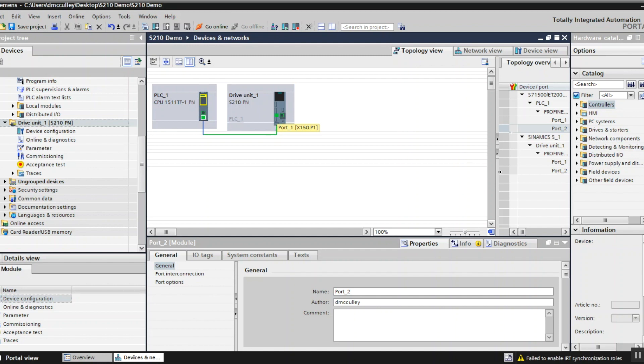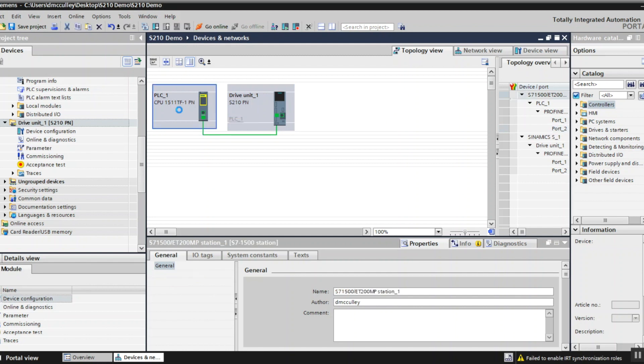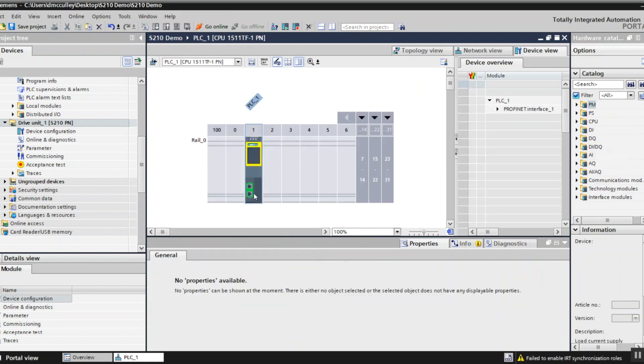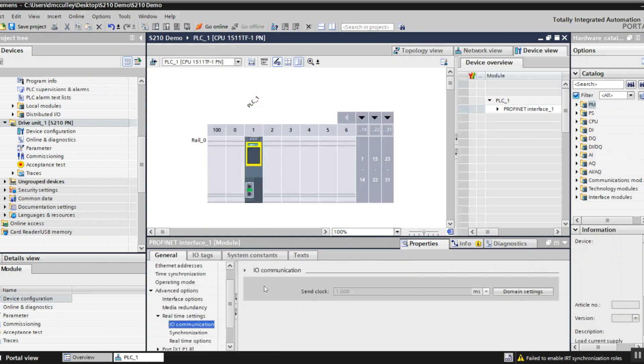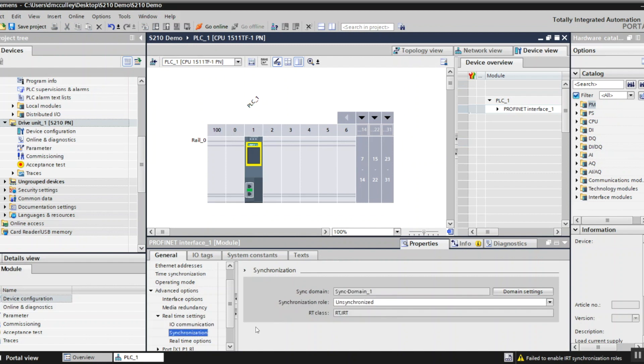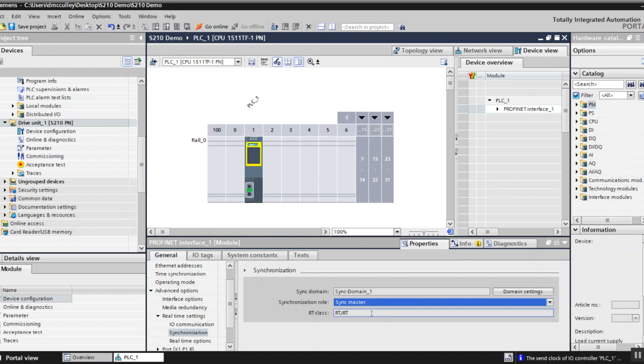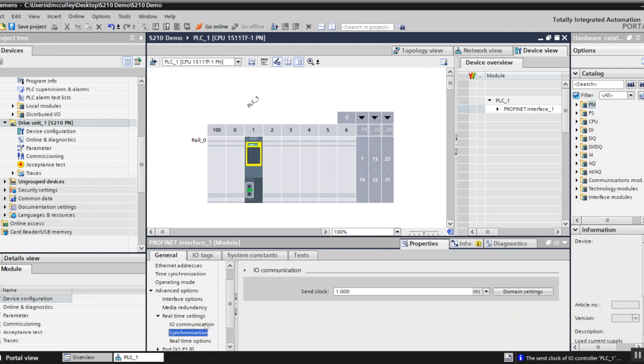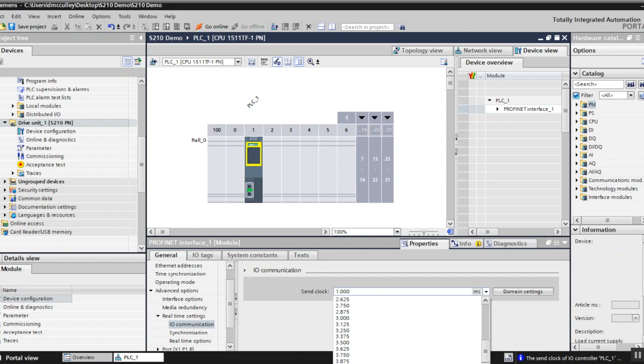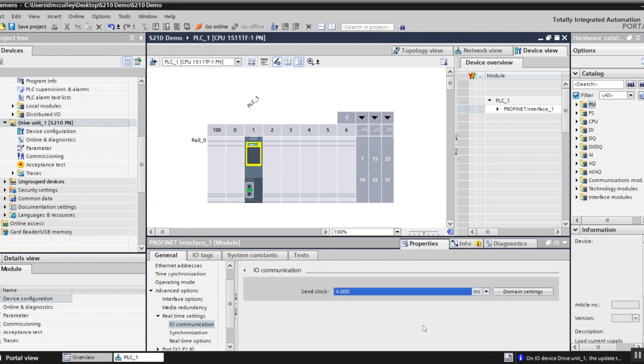Next I want to go to the device view of the PLC, so double click on it, click on the Profinet port, go to synchronization and I want to make it the sync master. When we use isochronous real-time, this is the master to the drive. I like to set the IO communication send clock to four milliseconds because if I keep it at one it's too fast and I can fault my PLC.